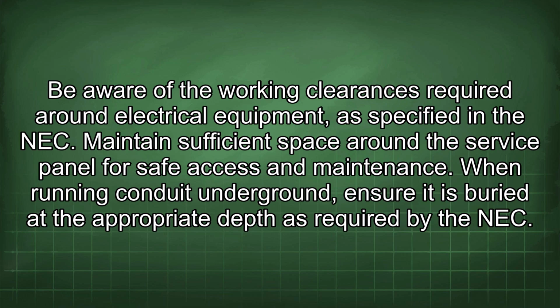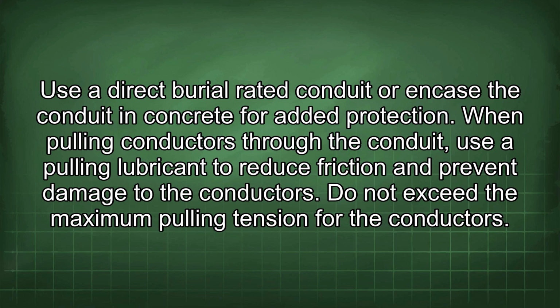When running conduit underground, ensure it is buried at the appropriate depth as required by the NEC. Use a direct burial rated conduit or encase the conduit in concrete for added protection. When pulling conductors through the conduit, use a pulling lubricant to reduce friction and prevent damage to the conductors. Do not exceed the maximum pulling tension for the conductors.